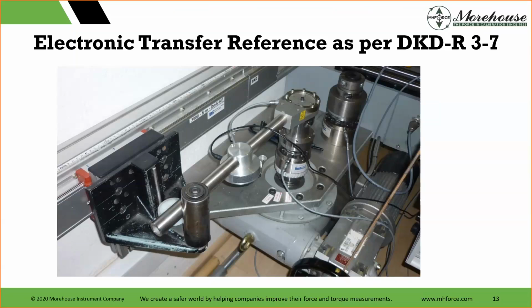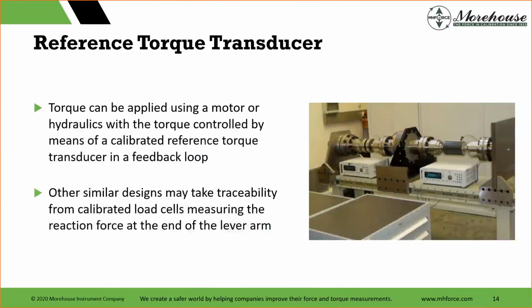So you really want to, if you do that and you get into it, you get to your PTs. And if you are sending something to, say, Morehouse, where we can say, hey, you want to know if your system's good or not good, you send us a torsion cell, we do it, you bring it back, you have the answer, and then you put it in your system, you can do an inter-laboratory comparison. The important part about those comparisons is to make sure you have the conversation, ideally with contract review, on how you're going to bolt this down. If you have a load cell or a torsion cell that needs bolted, loose versus tight bolting makes a big difference. So that's something you really want to quantify. The easiest thing to do is to tell the lab, hey, bolt these down to 10 Newton meters, 20 Newton meters. And then you can follow the process and everybody can align everything.